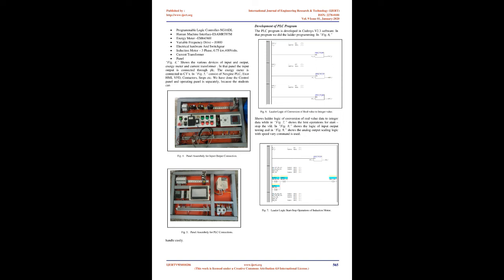The induction motor is cheaper and easier to maintain compared to other alternatives. The induction motor is made up of the stator, the stationary windings, and the rotor. The stator consists of a series of wire windings of very low resistance and it is permanently attached to the motor frame. The voltage and current is applied to the stator winding terminals and a magnetic field is developed in the windings. The stator windings are arranged so that the magnetic field appears to synchronously rotate electrically around the inside of the motor housing.